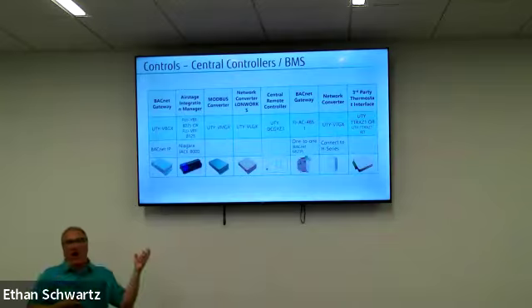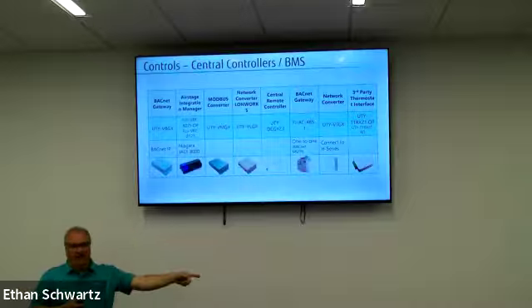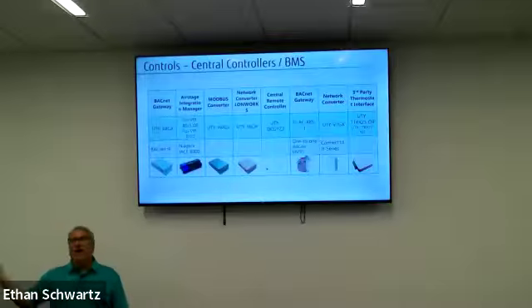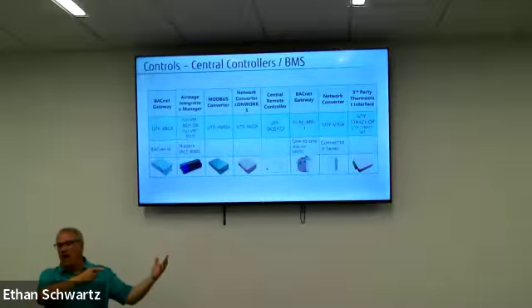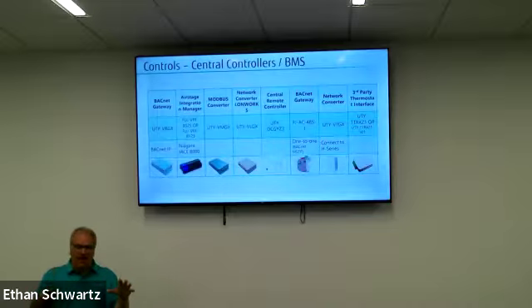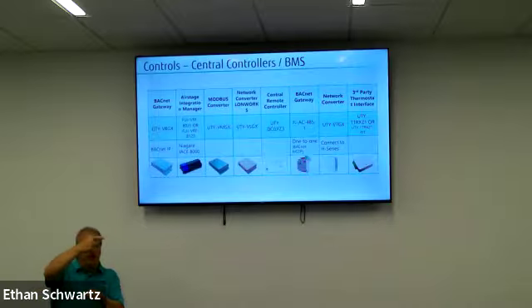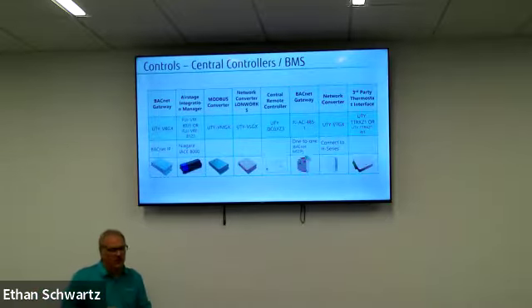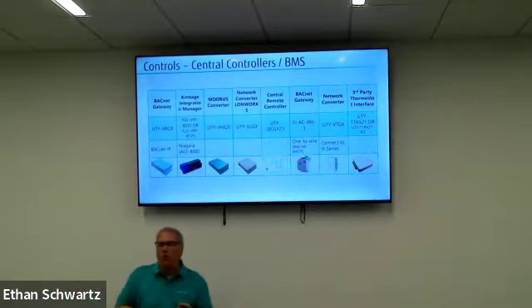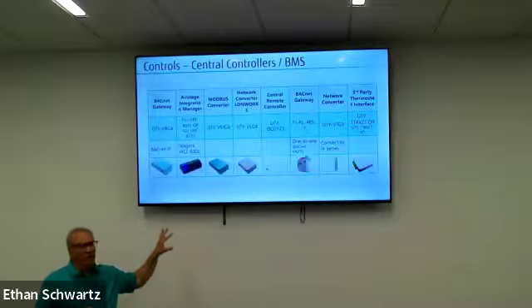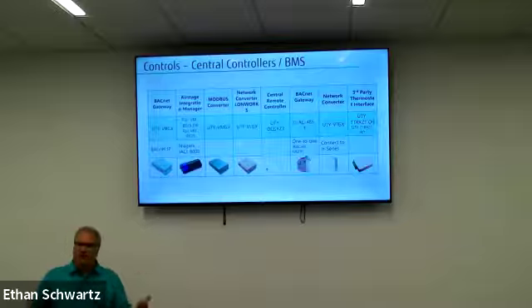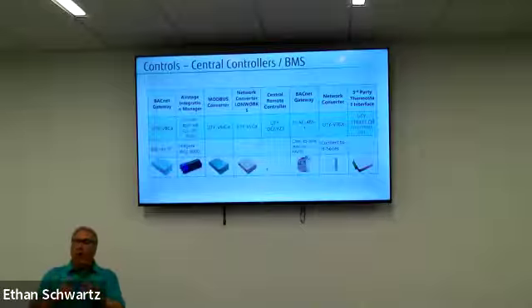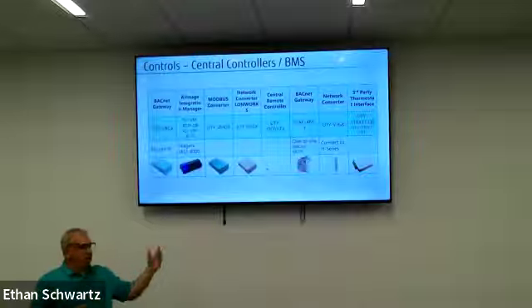The indoor unit looks at its return air thermistor and says, yeah, I'm away from set point, and I want to be 68. It sends a signal to the outdoor unit to start to open its EEV, and that compressor ramps up. Now we're ramping up, and then air blows on the Nest and everything looks good. Then it gets back down to below 72 and it takes that away. That ramp up and ramp down is where you lose some of the energy efficiency. So there's always a sacrifice when you deviate from the manufacturer's controls that it's selected for use with its equipment. Does that make sense to everybody? Because a lot of people don't realize that. And if you potentially have an oversizing situation with a mini split, then that can create a problem.